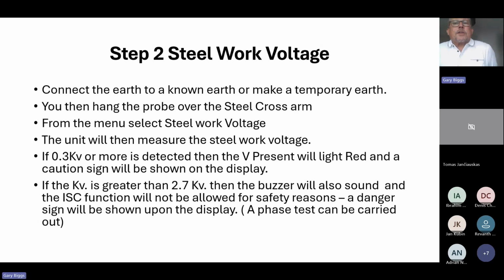So the next step is dealing with the steel work voltage, and as I described earlier, the wooden pole will normally have a steel cross member attached to the pole itself. That steel cross member is not earthed, and therefore that pole is not earthed other than it being buried in the ground itself. So between the cross member and the ground, as we said, you've got somewhere between 8 and 40 megohms of resistance. That depends on the age of the pole, the condition of the pole, the temperature, the humidity, precipitation. They will all have an effect on the resistance of that wooden pole, but essentially you're going to have a pole that is acting as an insulator.